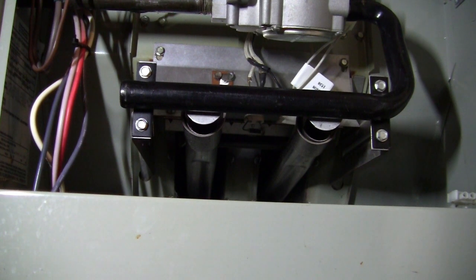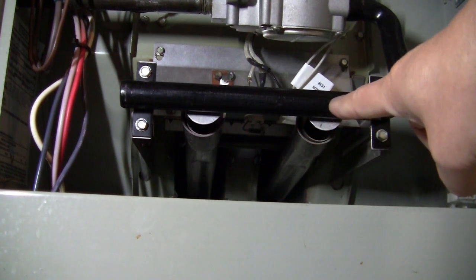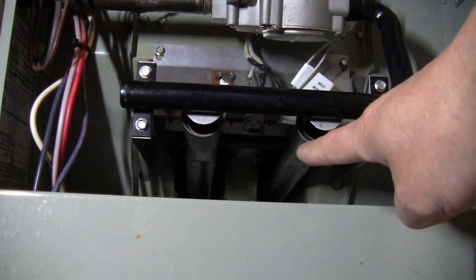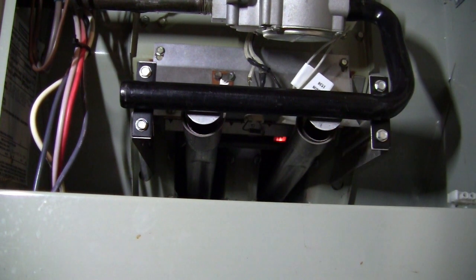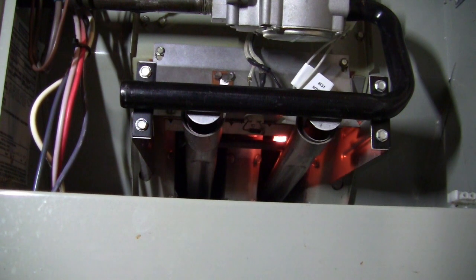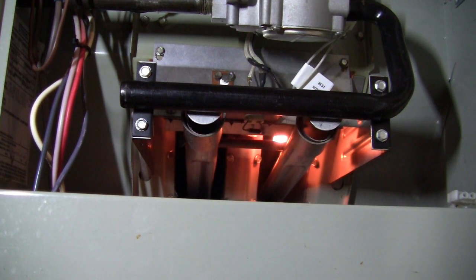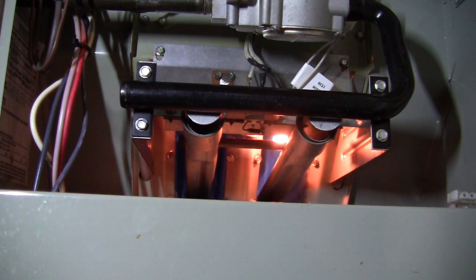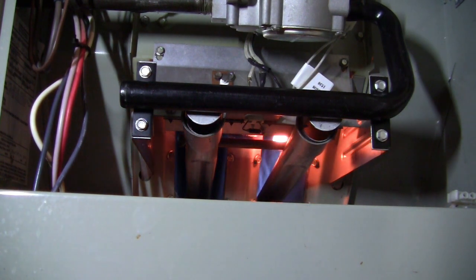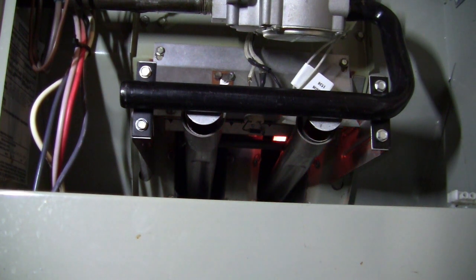As we said, this has, I believe, a 45-second delay for the igniter. The igniter down there, you will see, oh yeah, now it sends a signal to the igniter. It will be, see, red hot. After a couple of seconds, it sends the gas. 1, 2, 3, 4, 5. See? Five seconds later, the controller turns off the gas. I bet it's going to make another try, but I don't think we need to repeat it right now.